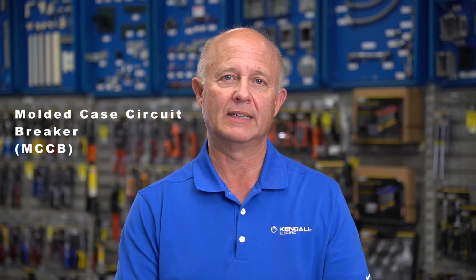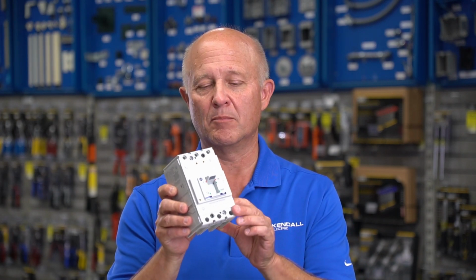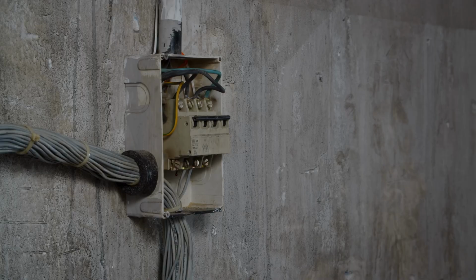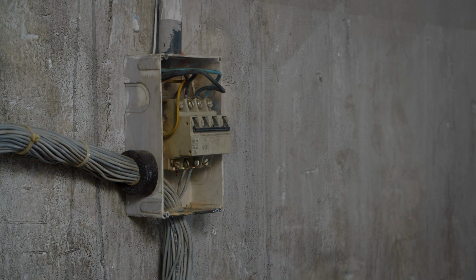So first up is the MCCB, which stands for molded case circuit breaker. Its name is derived from the fact that all of the electromechanical parts that make it work are housed inside a casing of molded plastic material. Now, these devices are specifically designed to protect downstream wiring and the connected hardware from any damage or destruction due to either a short circuit or a thermal overcurrent situation in the circuit.